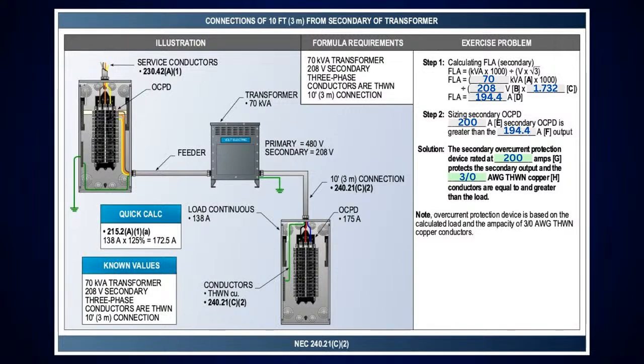So if I have a 70 kVA transformer, take that 70,000, and on the secondary I've got 208 volts times 1.732, which will give you 360. Divide by that 360 volts, I'm just rounding it up. That'll give you 194.4 amps. So at the minimum, that secondary has to be at least 200 amps. Yeah. Okay.